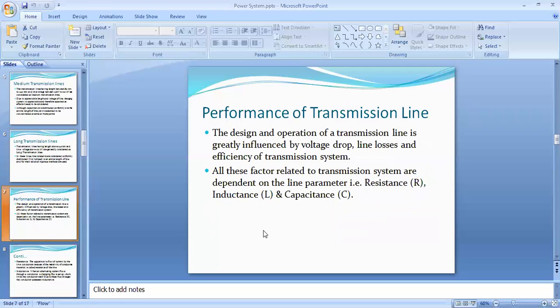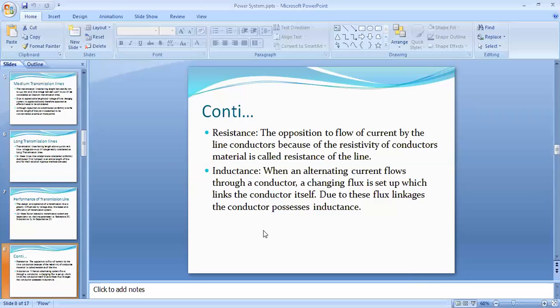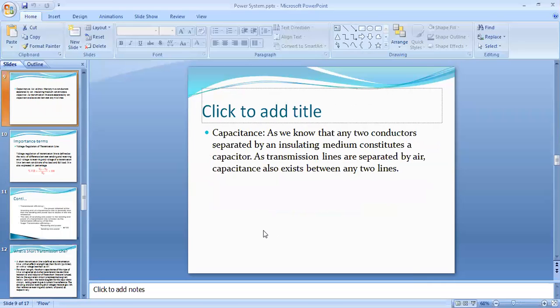The design and operation of transmission lines is greatly influenced by voltage transmission. All factors related to transmission systems are defined by line parameters: resistance, inductance, and capacitance. Resistance is the opposition to flow of current due to the resistivity of the conductor material. When alternating current flows through a conductor, a changing flux is set up which links the conductor, giving it inductance. Capacitance exists between two conductors separated by an insulating material — in a transmission line, the conductors are separated by air.